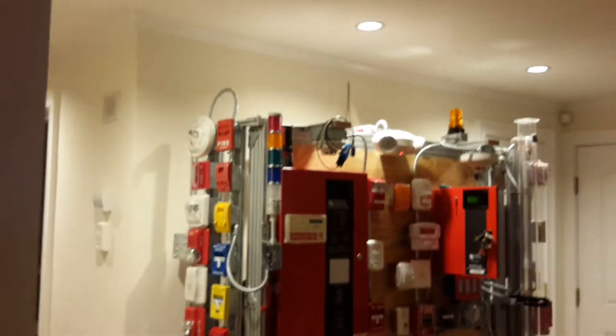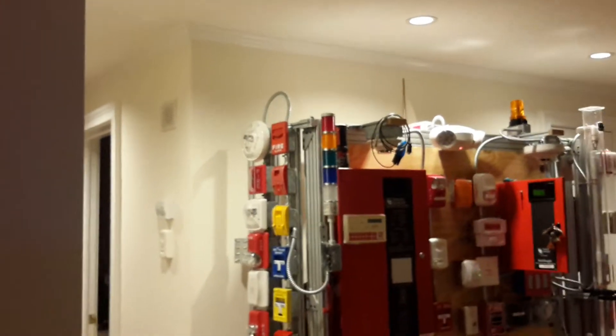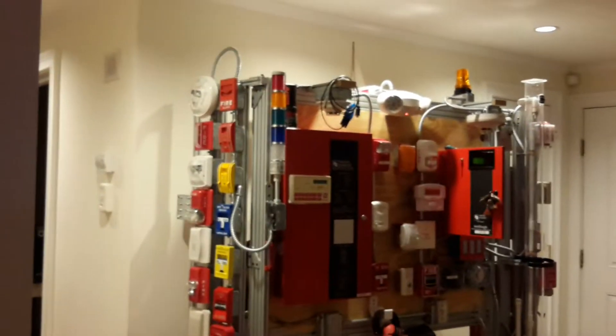The red light's going to turn on because of the alarm circuit. Any smoke detector or pull station that is tripped will send the alarm circuit to the panel, and the red light's also going to be tripped. If it's the suppression system, it's going to be red and white — white indicating suppression.